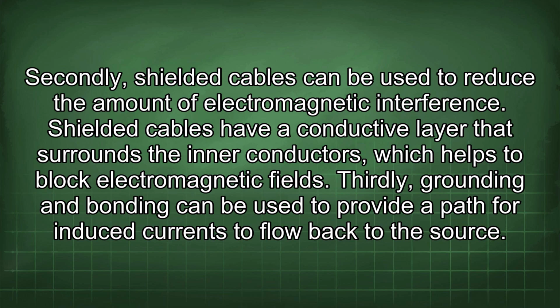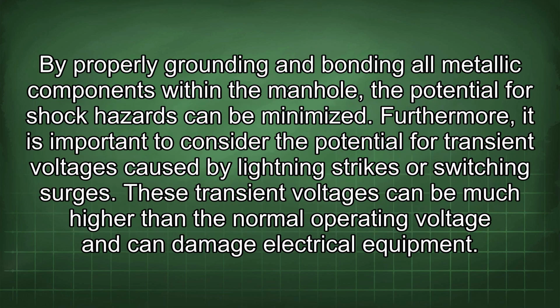Thirdly, grounding and bonding can be used to provide a path for induced currents to flow back to the source. By properly grounding and bonding all metallic components within the manhole, the potential for shock hazards can be minimized. Furthermore, it is important to consider the potential for transient voltages caused by lightning strikes or switching surges. These transient voltages can be much higher than the normal operating voltage and can damage electrical equipment.